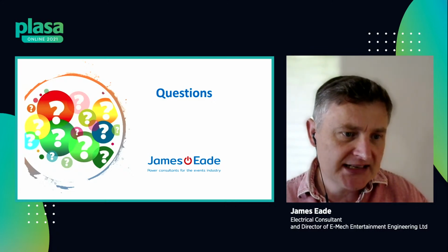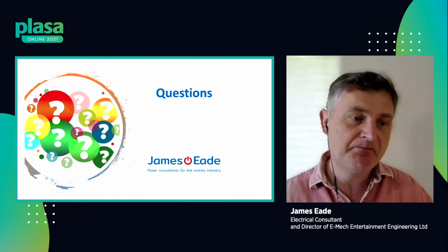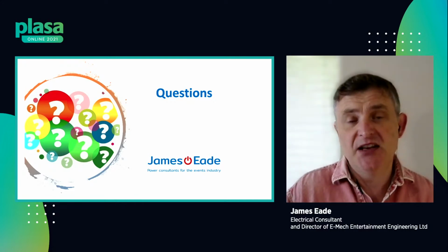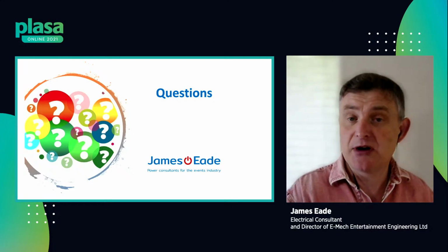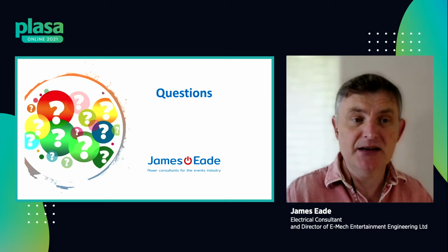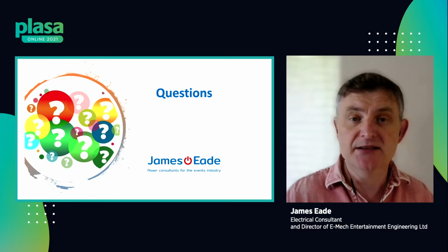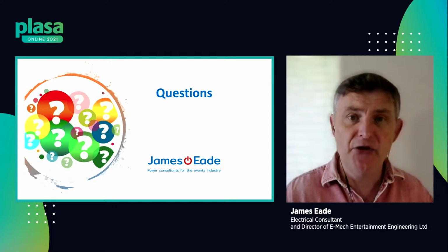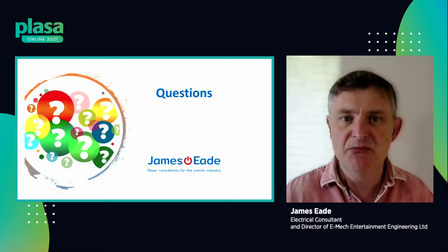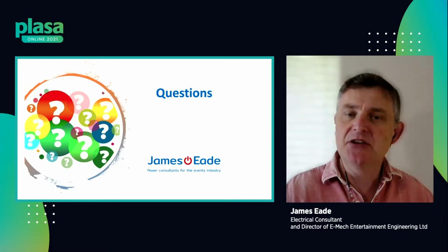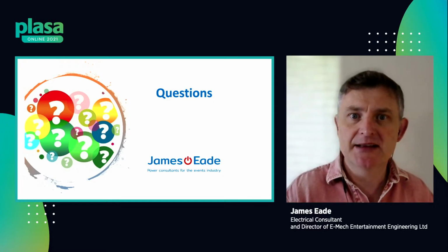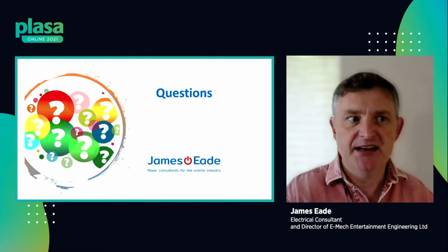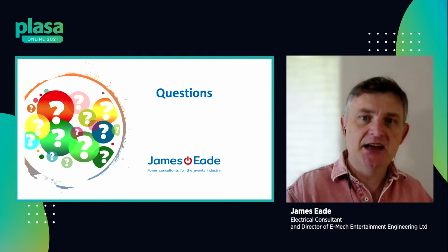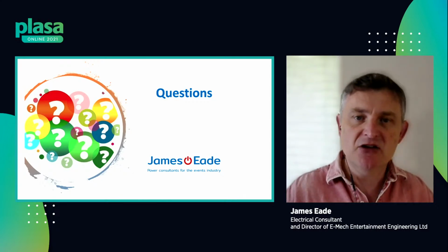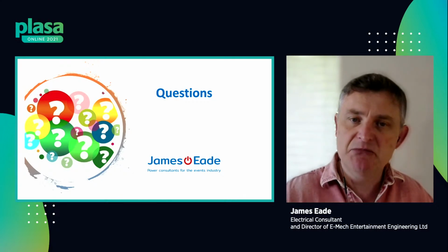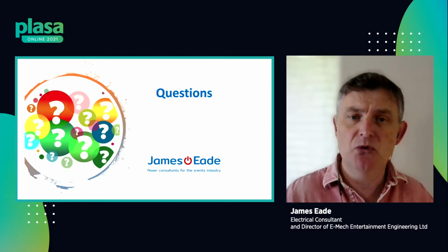What periodic electrical testing is required for electric hoists and winches, from Douglas? Again, it depends on use. If it's a rental company, I'd suggest it's good practice, as with any rental company, to check everything either when it comes back off a job or before it goes out. If it's in your own venue and used once in a blue moon, then test it once in a blue moon, but carry out visual inspections more often, because damage is likely to come from rats chewing through cables or another bit of equipment swinging across and chafing cables or similar.